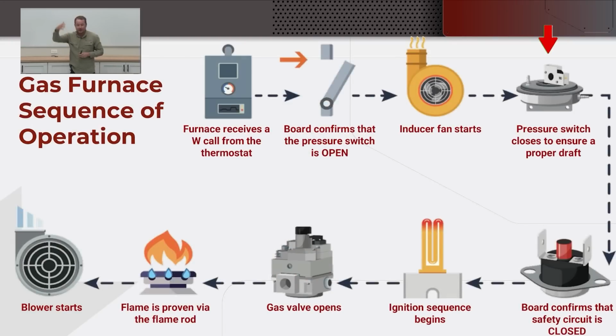Did a bird build a nest in the flue, right? Did the thing somehow get full of water because of condensation or because the cap fell off and water ran down in? You'll find cases where the tube is bent or kinked or damaged or broken or has something blocking it. There's all these things that happen. It's almost never the switch. Again, it's sometimes the switch, but you don't start with the switch. It's just like saying, I think it has a bad compressor.